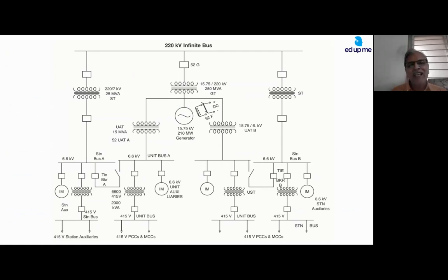For the boiler, for giving water to the boiler, you need a boiler feed pump, the largest pump in the power plant. It's a mini power plant. The pump itself is a mini power plant. In a 210 megawatt generator, we are using 3 BFPs, each of 4 megawatt, 4,000 kilowatt, some 5,000 HP. A very large motor, and it has many protections, many auxiliary circuits. How the power is generated is a subject by itself, for some other time.